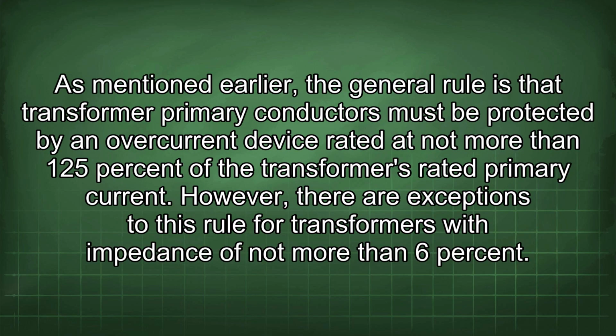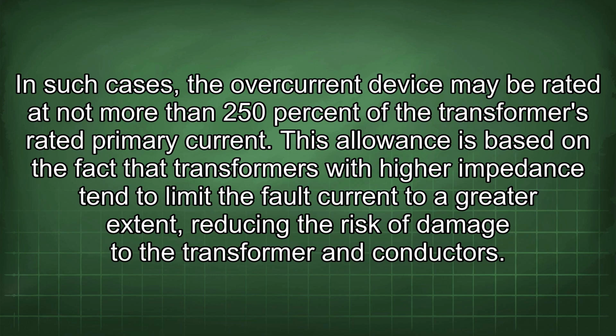As mentioned earlier, the general rule is that transformer primary conductors must be protected by an overcurrent device rated at not more than 125% of the transformer's rated primary current. However, there are exceptions to this rule for transformers with impedance of not more than 6%. In such cases, the overcurrent device may be rated at not more than 250% of the transformer's rated primary current. This allowance is based on the fact that transformers with high impedance tend to limit the fault current to a greater extent, reducing the risk of damage to the transformer and conductors.